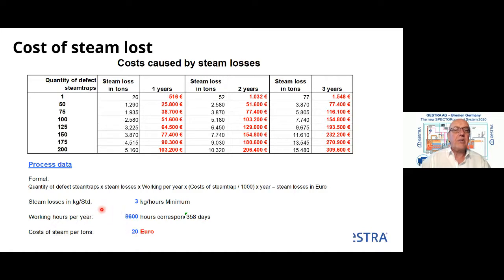Steam losses which we can measure with our ultrasonic system, which we offer to measure the loss of steam, start really at 2 kilograms to 3 kilograms, then we can say there is a real loss and a problem with the steam trap. But if we take these three numbers together and we have 1 steam trap, then the steam lost in 1 year is already 26 tons. 26 tons multiplied by 20 euro is 516 euro loss of energy in the first year.